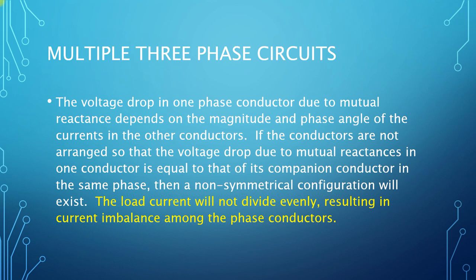If the conductors are not arranged so that the mutual reactances are equal, the conductors form a non-symmetrical configuration. In a non-symmetrical configuration, the load current will not divide equally between the parallel circuits, and this results in current unbalance among the phase conductors.